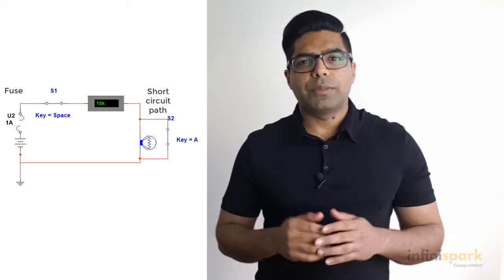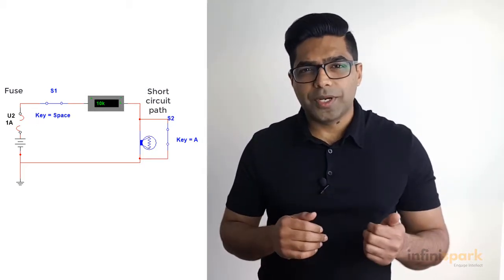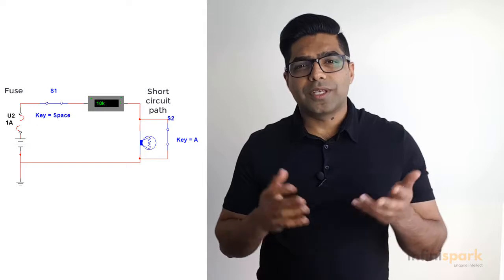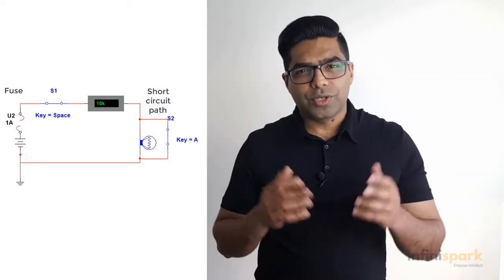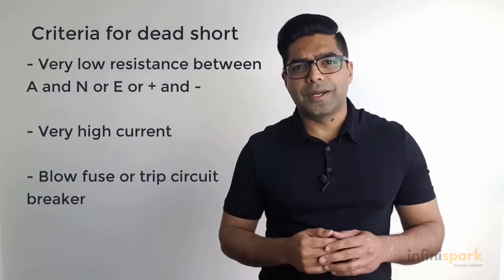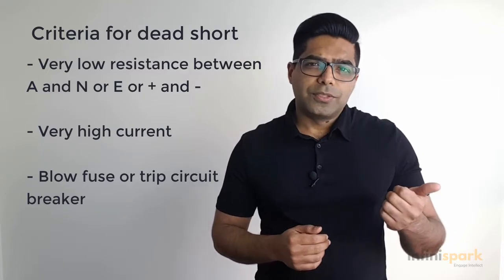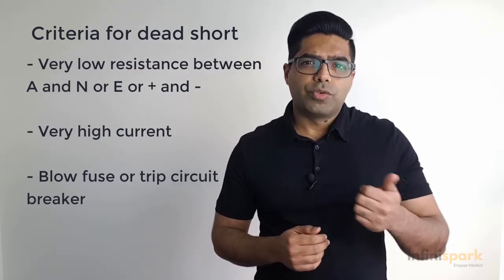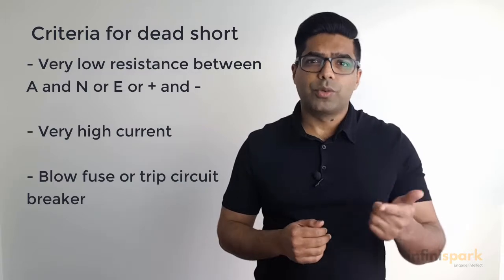The most likely outcome of this situation is a tripped circuit breaker or a melted wire because the current is too high. So the criteria for a dead short fault are: very low resistance between live conductor and neutral or earthing conductor, very high current which causes a circuit protection device to operate.